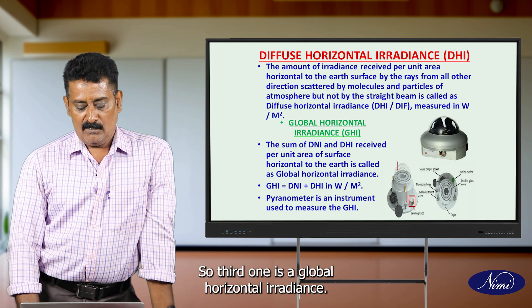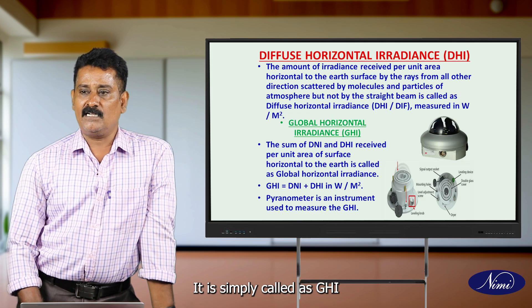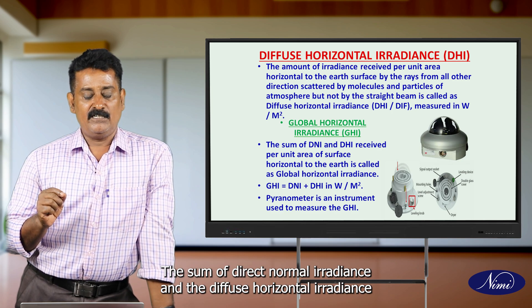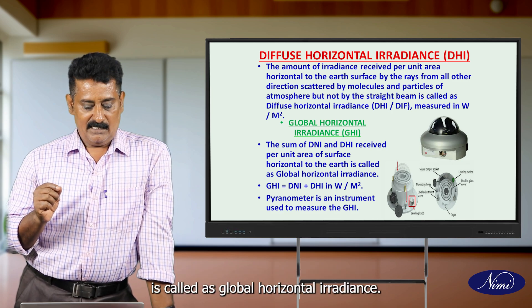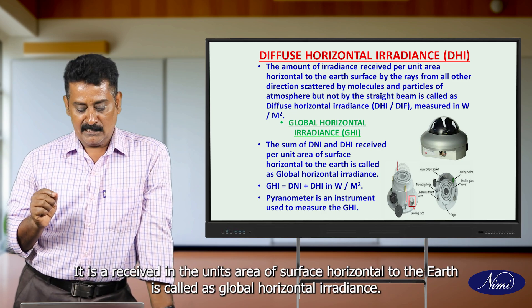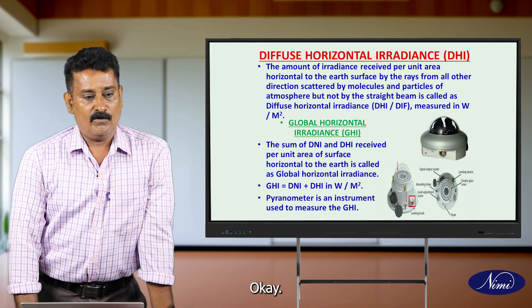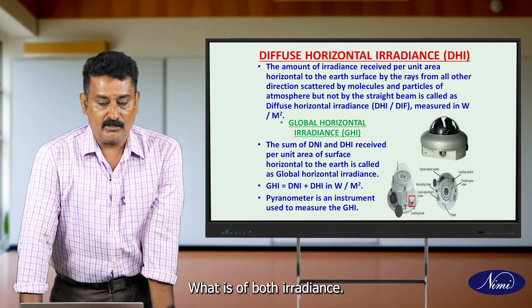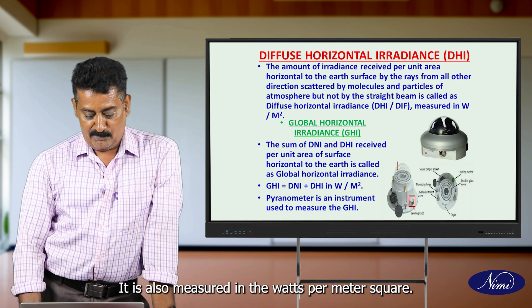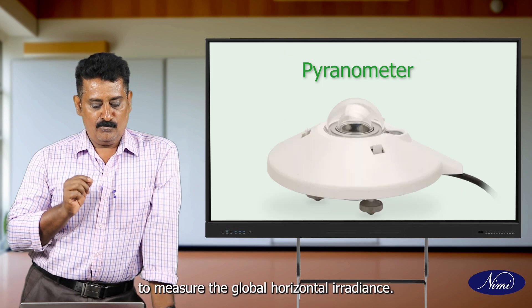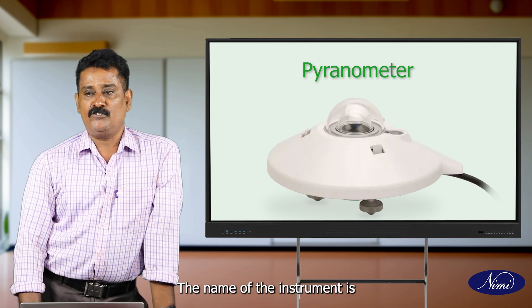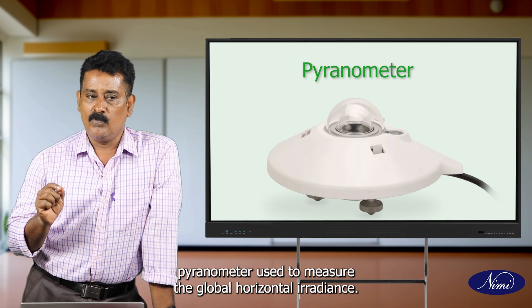The third one is global horizontal irradiance, simply called GHI. The sum of direct normal irradiance and diffuse horizontal irradiance is called global horizontal irradiance. It is also measured in watts per meter square. There is one instrument used to measure the global horizontal irradiance — the name of that instrument is pyranometer.